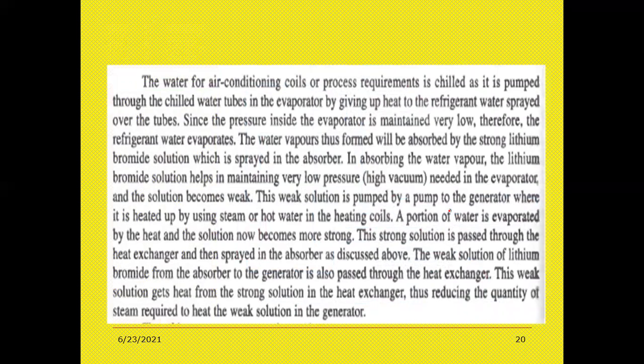Since the pressure inside the evaporator is maintained very low, the refrigerant water evaporates. The water vapors thus formed will be absorbed by the strong lithium bromide solution, which is sprayed in the absorber. In absorbing the water vapor, the lithium bromide solution helps in maintaining the very low pressure needed in the evaporator. This weak solution is pumped by the pump to the generator, where it is heated up by using the steam or hot water in the heating coils.